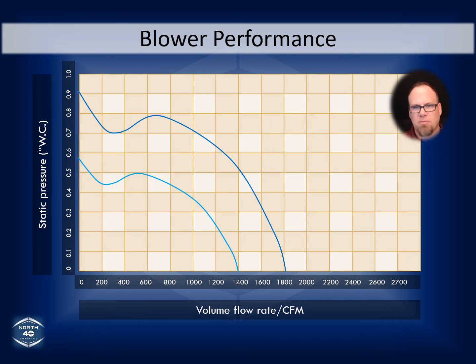Okay, one of the biggest problems that we have, we go out and we put in a brand new furnace, and that brand new furnace is set up to the nines by the efficiency programs that are out there, by the standards that the manufacturers give and the industry gives. So we do everything right. When we leave, the customer goes out and buys a $30 really restrictive filter, puts it in place of the one that we have, which is probably going to be either a 4-inch filter or a fiberglass type filter. And they totally change all the dynamics because they've really restricted that airflow now.